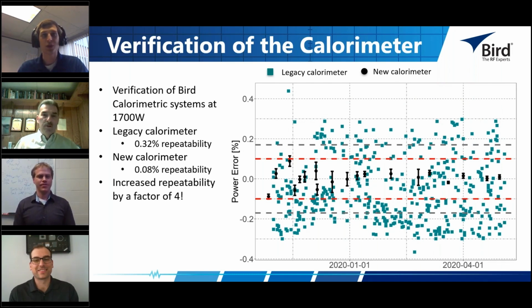One comment before you go there, Jacob. Just wanted to say that Bird's been making calorimeters for a very long time, even long before my time, if you can believe that. But the reason why Bird used calorimeters in days gone by is that calorimeters measure heating power, which is the true definition of the watt. The true definition of power is the power to produce some level of heat.